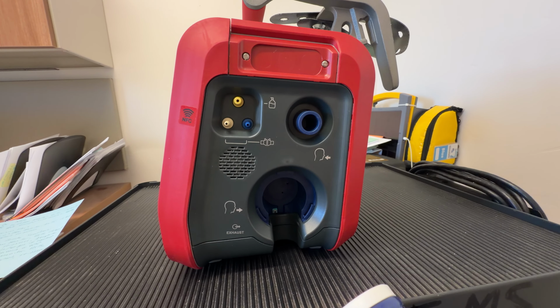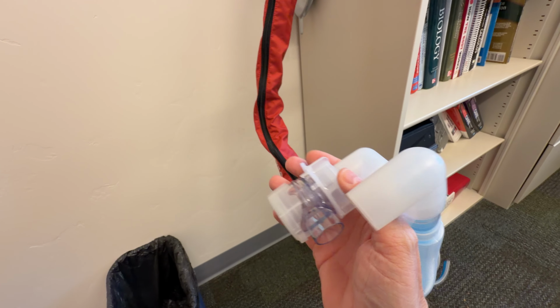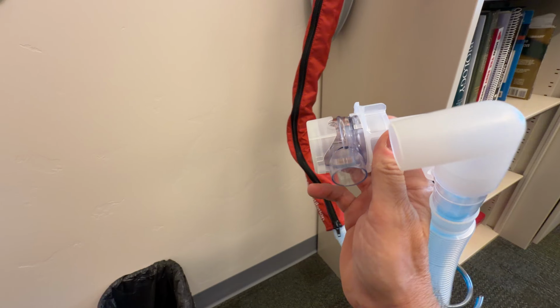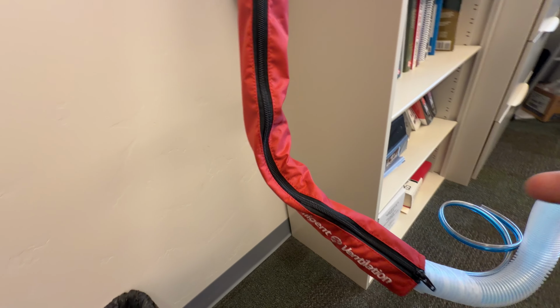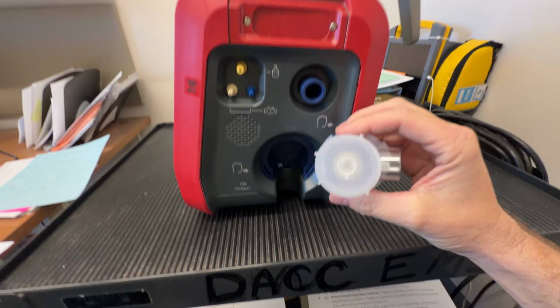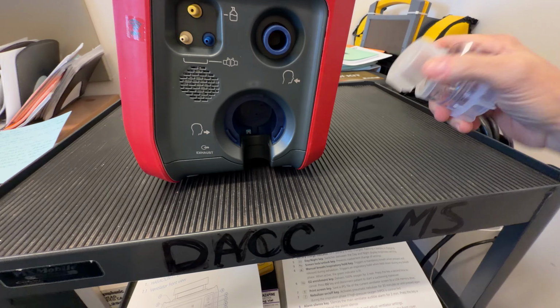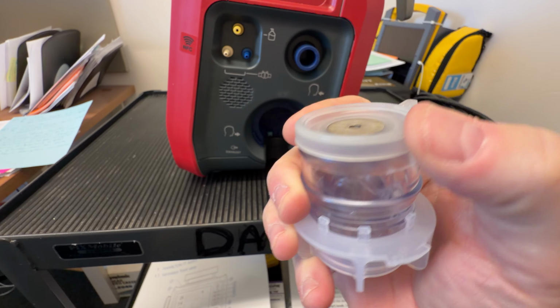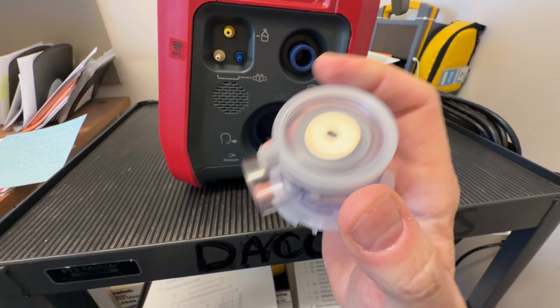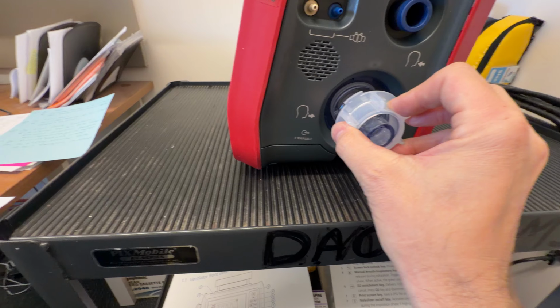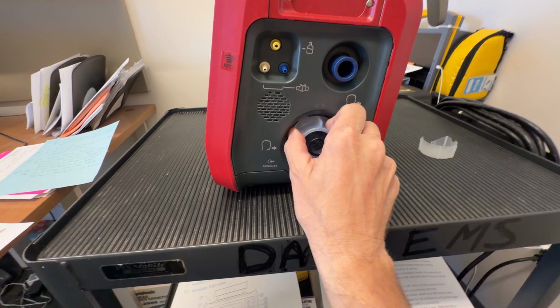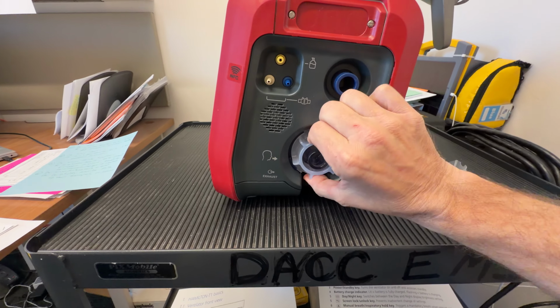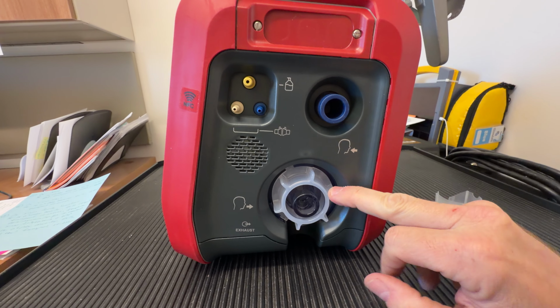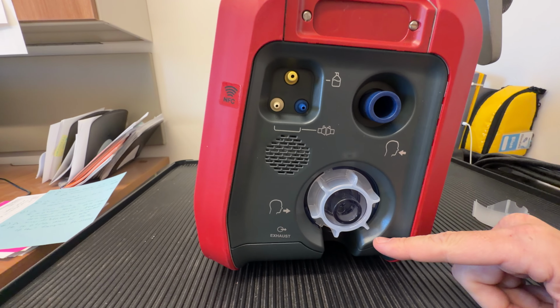So when you're actually using your vent tubing on your patient, you're probably going to want to use the expiratory valve that comes with it. So it'll come attached to the expiratory limb of your tubing. So what you'll do is you'll just remove it, bring it over to your ventilator. There's going to be a cap, and you want to remove that cap, and you want to check and make sure that this membrane seal is intact, and then the membrane seal will go into the ventilator, and then righty-tighty, lefty-loosey, tighten it down. You'll get a click, and now your expiratory port has been installed, and you can attach the tubing. So this is your inspiratory and your expiratory attachment point.